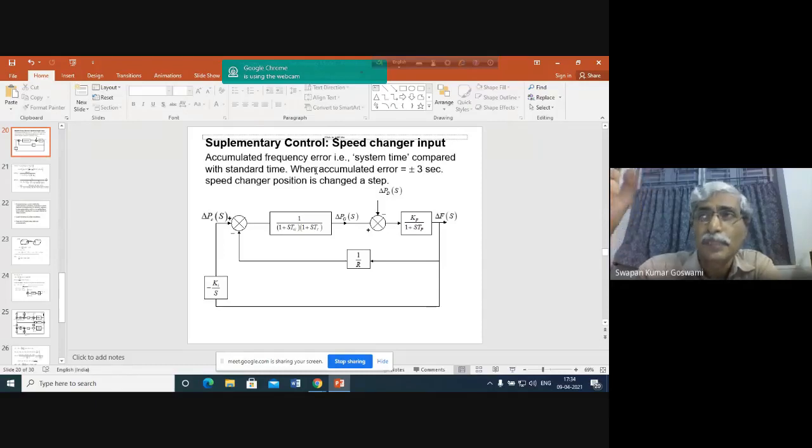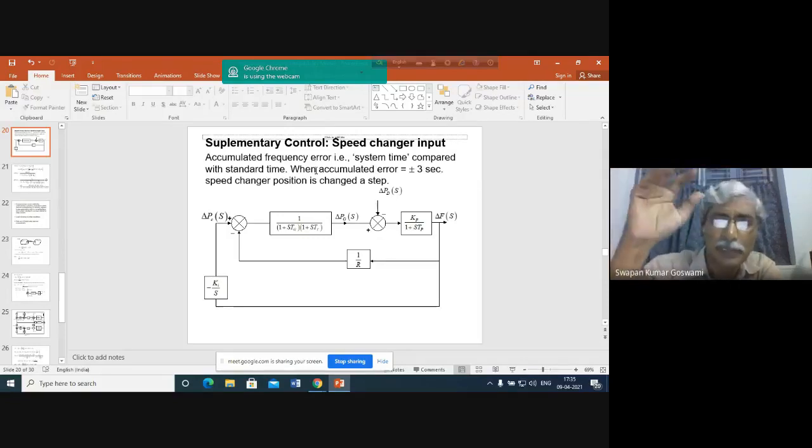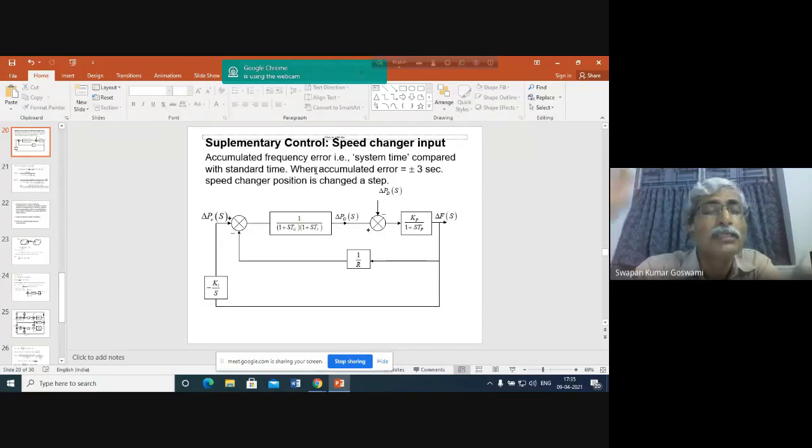If you support the system by drawing undeclared power when the frequency is high, then you will be rewarded. You may get power even for free. But if you supply undeclared power during that time, then you will get no price at all.